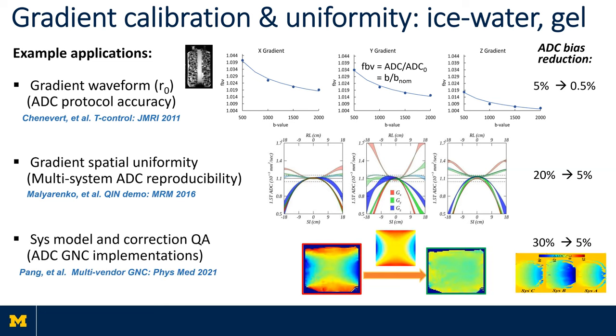The gel flood phantom that provides 2D mapping is useful for QC of emerging vendor implementations of bias correction on clinical systems, which can be a black box otherwise. This can help to compare to gradient models and improve B-value uniformity from individual systems, as well as reduce cross-system variability, similar to the previous example.